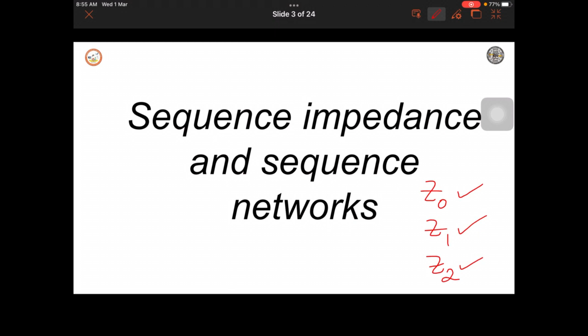When only positive sequence currents are present, the impedance is positive sequence impedance. Similarly, when negative sequence currents are present, the impedance is called negative sequence impedance, and zero sequence impedance is the one in which zero sequence currents are present.